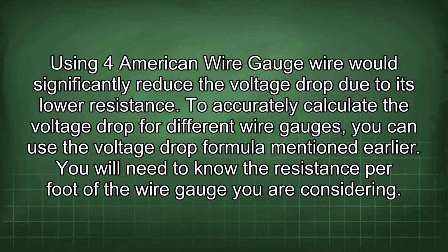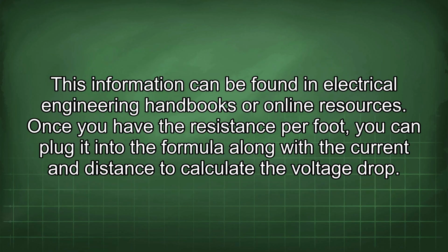To accurately calculate the voltage drop for different wire gauges, you can use the voltage drop formula mentioned earlier. You will need to know the resistance per foot of the wire gauge you are considering. This information can be found in electrical engineering handbooks or online resources. Once you have the resistance per foot, you can plug it into the formula along with the current and distance to calculate the voltage drop.